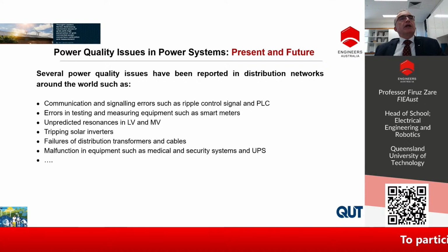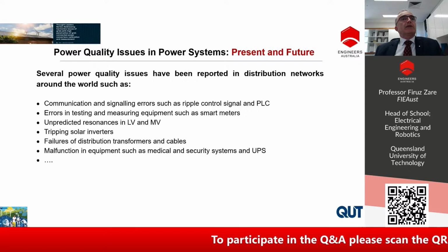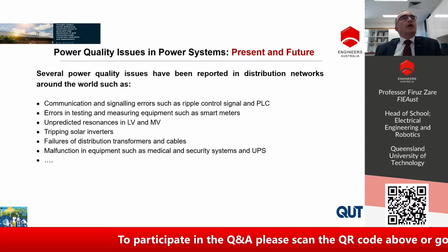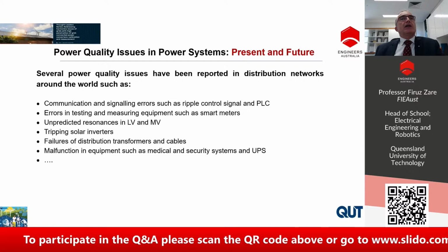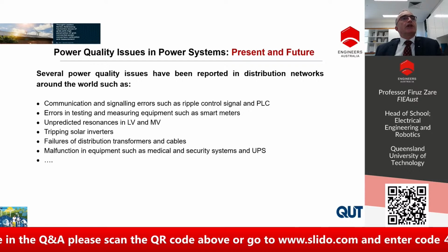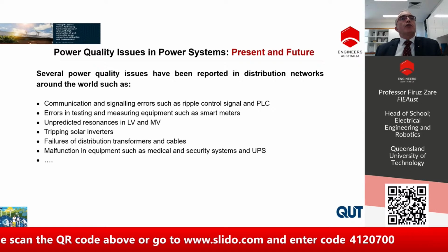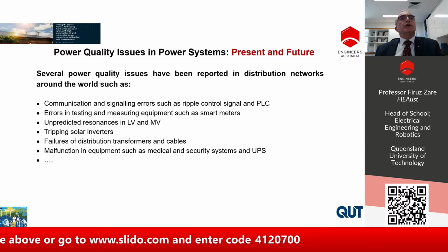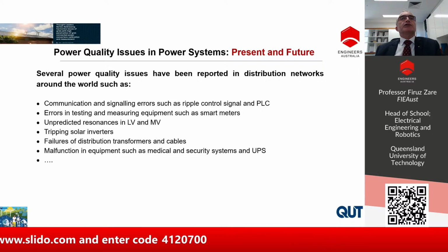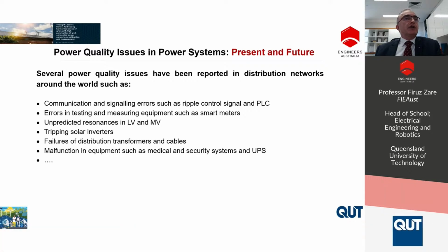Based on the collaboration that we had with different standardization committees and also with manufacturers and some companies, we have realized that there have been lots of reports regarding communication and signaling errors for some of the equipment in distribution networks, like ripple control signal and PLC, especially in Europe, because of the frequency below 150 kilohertz. And for some of the measuring devices like smart meters, we have seen some reports in terms of wrong measurement or significant errors in the measurement.